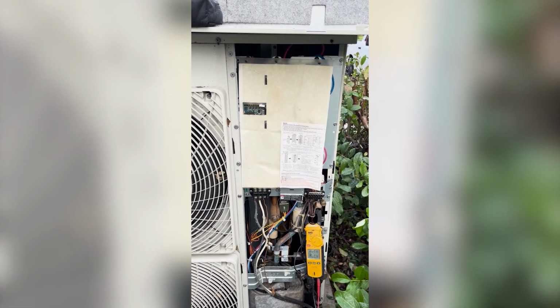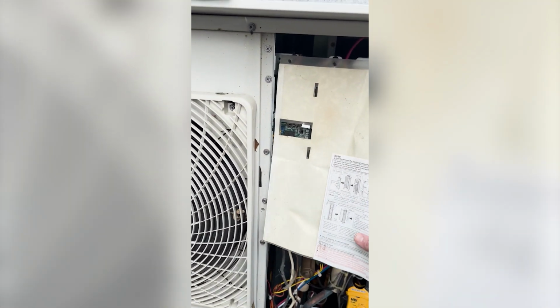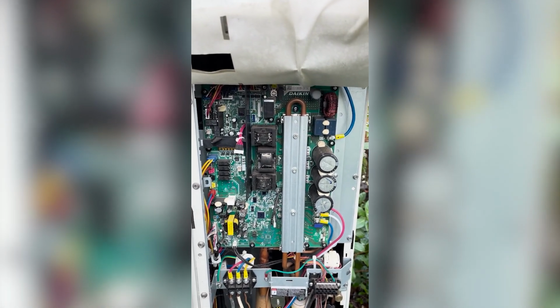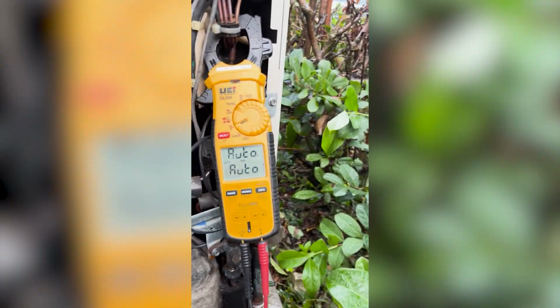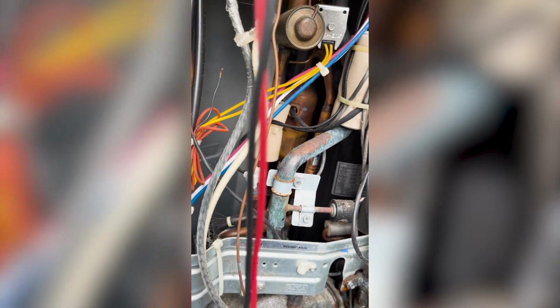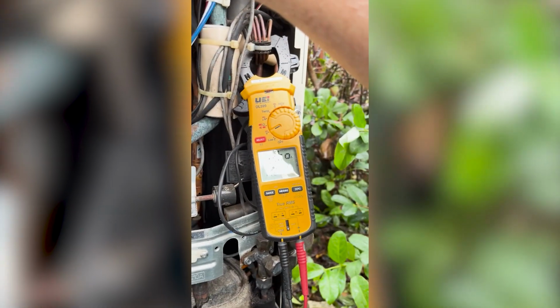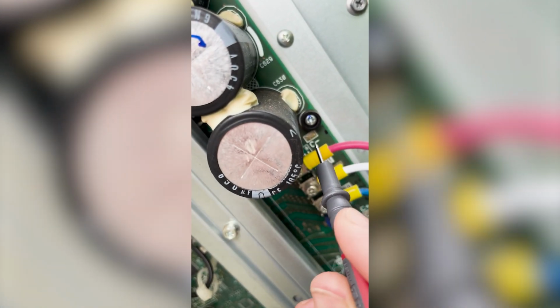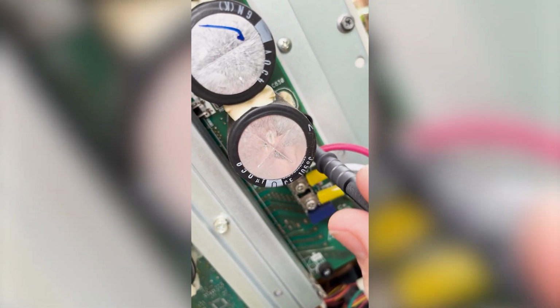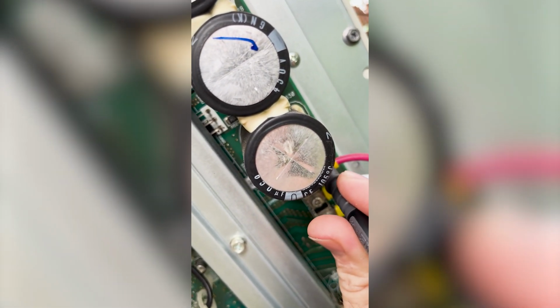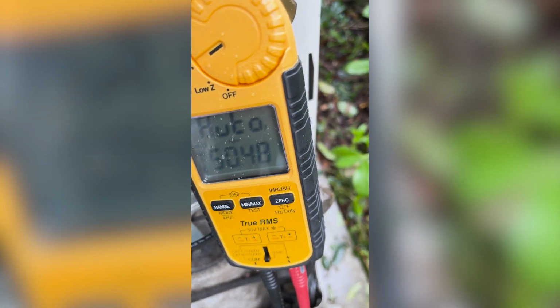Now I know that they're complicated, and that what you can see here can be somewhat intimidating and confusing, but there's a safety aspect of this. So if we come here and we look, my meter's set to auto for the high voltage aspect, right? I have nothing. But what we should be checking here is actually our C plus and our C minus terminals. And you will actually find here C plus, C minus. I have 50 volts.